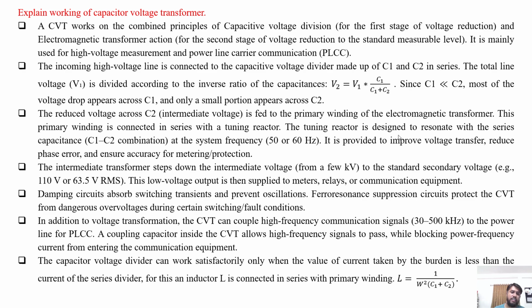The capacitor voltage divider can work satisfactorily only when the value of the current taken by the burden, that is the secondary circuit impedance connected in the secondary side of the potential transformer, is less than the current of the series divider. For this, an inductor L is connected in series in the primary circuit, whose value can be determined with the equation L is equal to 1 upon omega square into C1 plus C2, where omega is the angular frequency 2 pi f. So this is how the working of the capacitor voltage transformer is understood.